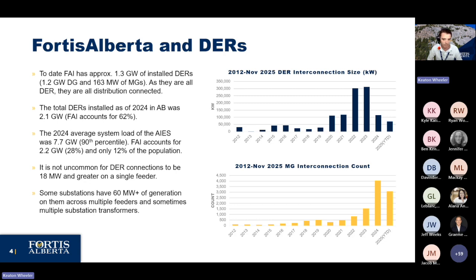I've put a few graphs up here showing how often we're getting these installations in and what our install capacities are each year. Generally speaking, we're seeing exponential increases, in particular with MGs at the moment, with very high penetration levels. It's very common for us to see substations that now have 60 megawatts and above on them, creating some very significant operational challenges.